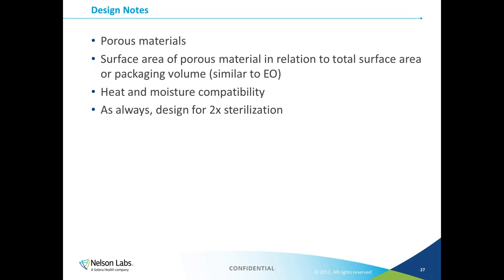Let's look at a few design notes for steam sterilization. In order for the kill mechanism to take place, steam must come into contact with the medical device and condense back into water, releasing the latent energy — so porous material is necessary and essential. For the same reason we need a good ratio of porous to non-porous material in EO, we have the same requirements for steam. The more porous your packaging, the more opportunity steam has to penetrate. The materials selected for packaging must be compatible with high heat — we typically see about 121 to 132 degrees Celsius with humidity and moisture. And always design for double sterilization in case of a failure and need to re-sterilize — the same as for every other sterilization mode.